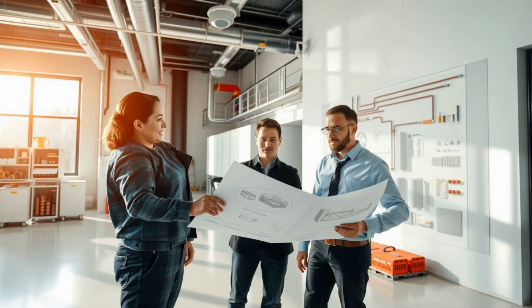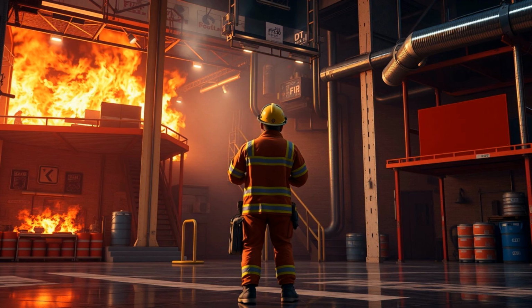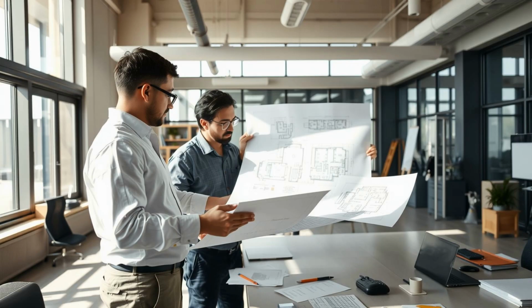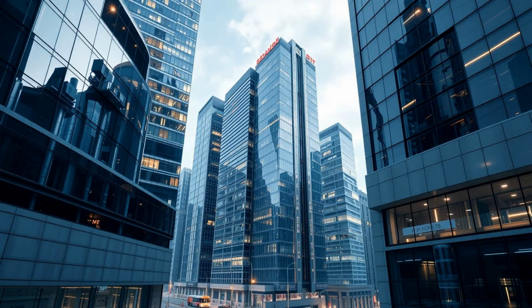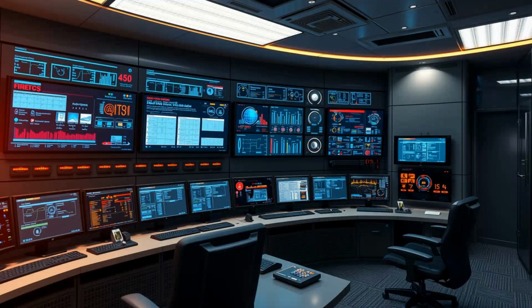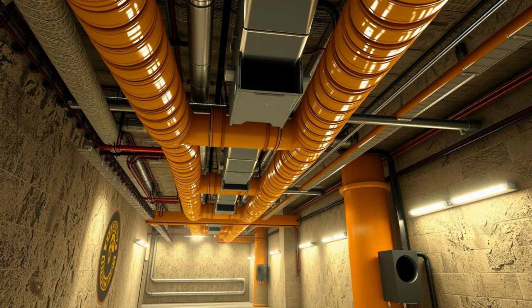Designing an effective fire protection system is a specialized task that involves more than just equipment selection. It begins with a thorough risk assessment, taking into account the building type, occupancy load, material hazards, and applicable fire codes. This is followed by layout planning, hydraulic calculations for water-based systems, and the integration of all components into a single cohesive strategy. Modern buildings also require fire systems to work in tandem with HVAC systems, building management systems (BMS), access control, and emergency lighting. The coordination between all these systems is essential to ensure that fire protection doesn't become a source of confusion during emergencies. For instance, the smoke exhaust system must not conflict with pressurization fans, and emergency lighting must remain operational even when power is disrupted.